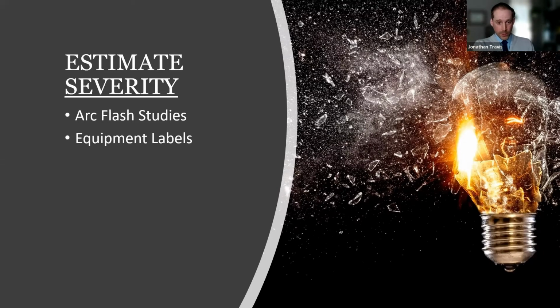So what incident energy do I have? What arc flash or what voltage level do I have? Anytime we're working above 30 volts, and this is coming from the standards, we could have a shock hazard that could cause a fatality. I think the number one cause of electrical fatalities in North America is shocks from 120 volts. So the statistics back it up.